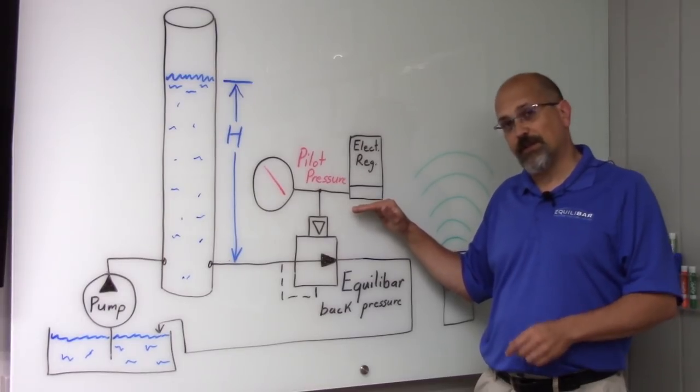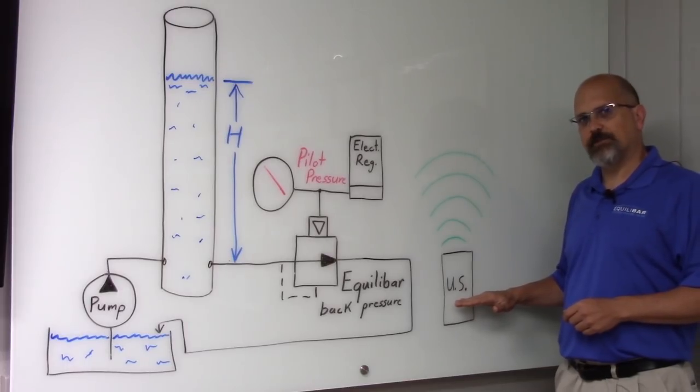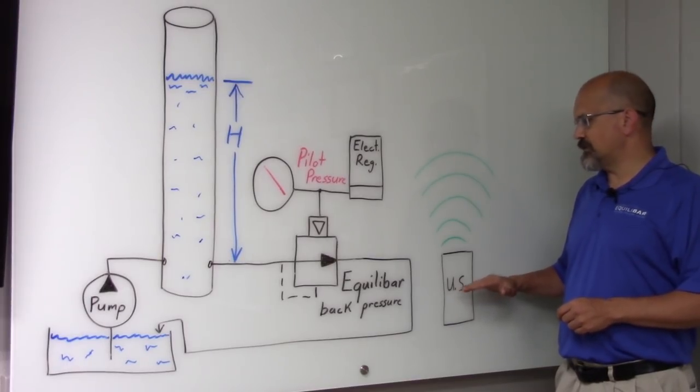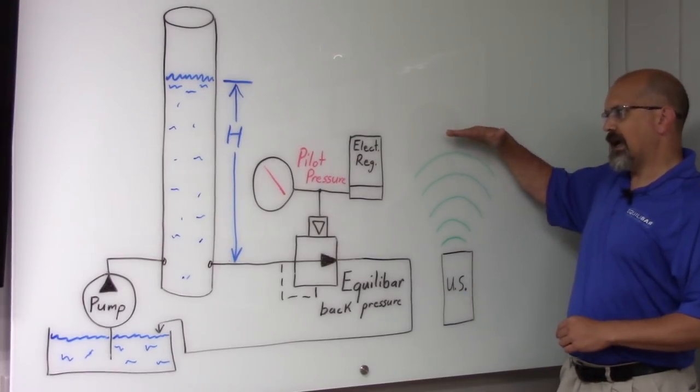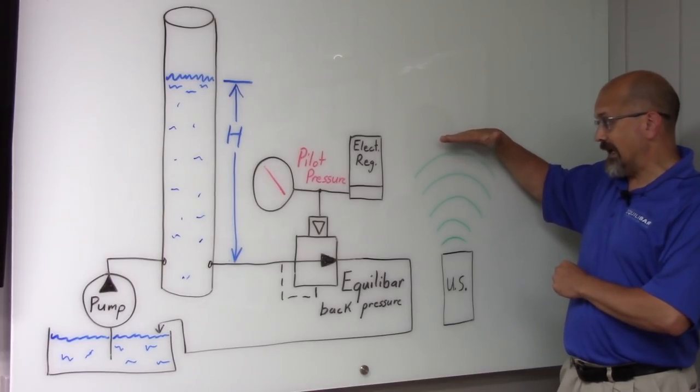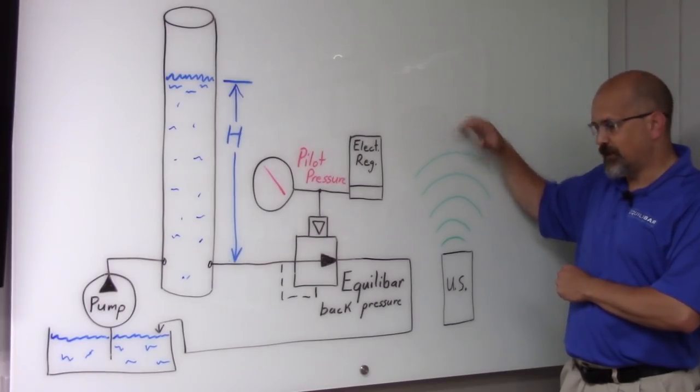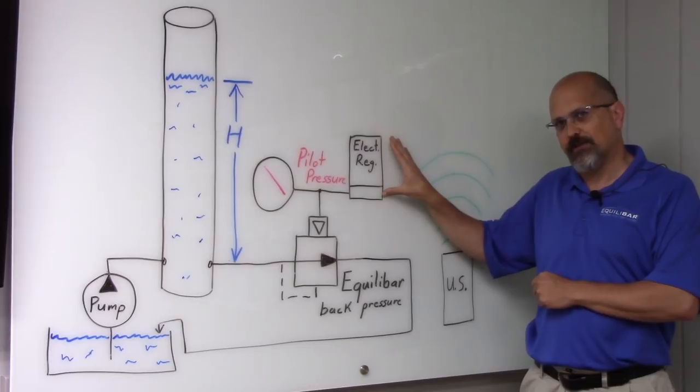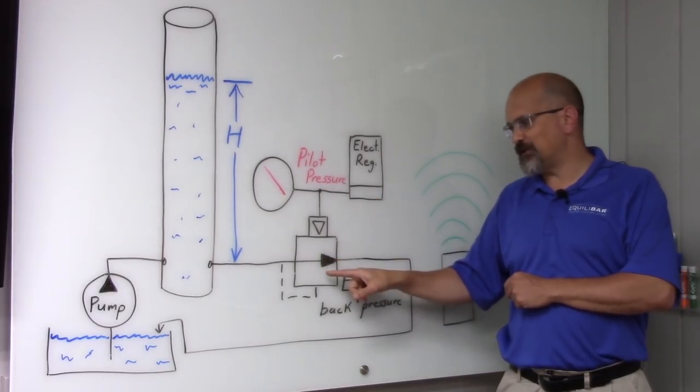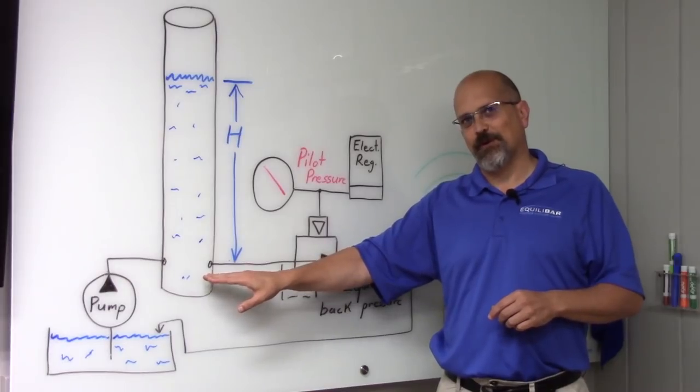The electronic pressure regulator set point comes from an ultrasonic sensor, and that ultrasonic sensor measures distance. For the demonstration, I'm going to use my hand to set the level of the ultrasonic sensor, which sets the command to the electronic pressure regulator, which sets the pilot pressure to the back pressure regulator, which then controls the pressure in the water column.